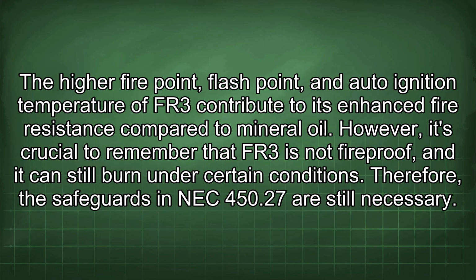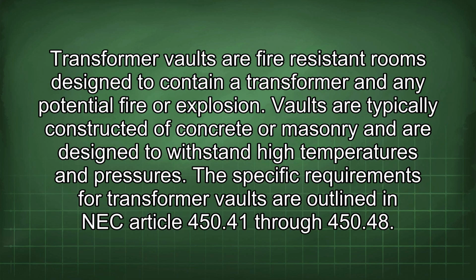The higher fire point, flash point, and auto-ignition temperature of FR3 contribute to its enhanced fire resistance compared to mineral oil. However, it's crucial to remember that FR3 is not fireproof and it can still burn under certain conditions. Therefore, the safeguards in NEC 450.27 are still necessary. Transformer vaults are fire-resistant rooms designed to contain a transformer and any potential fire or explosion.